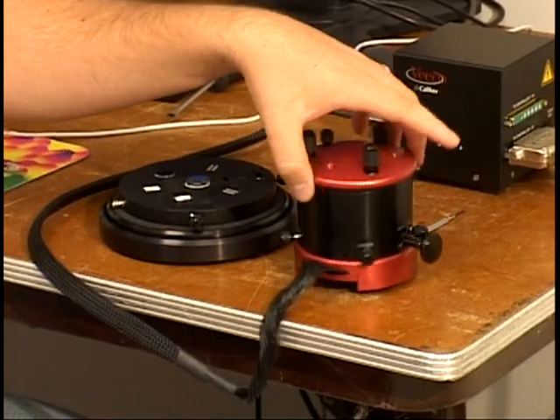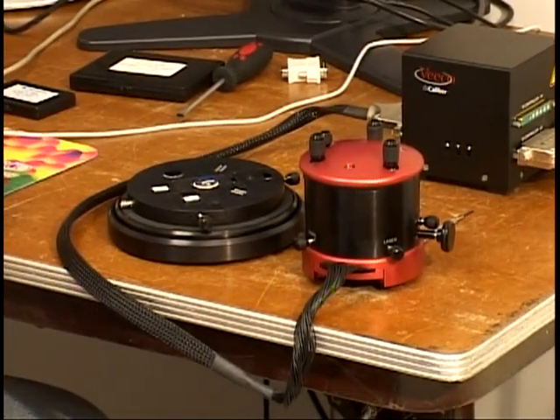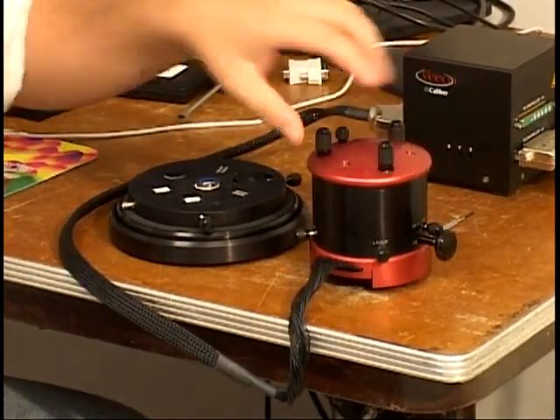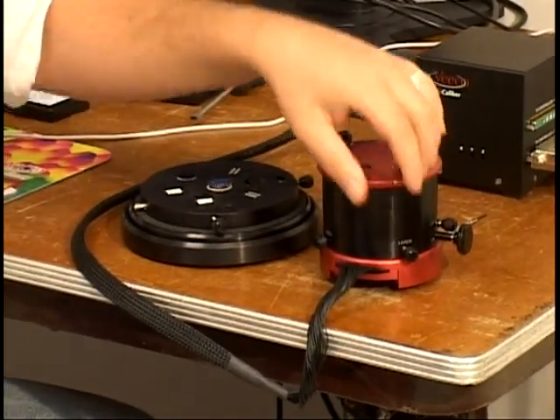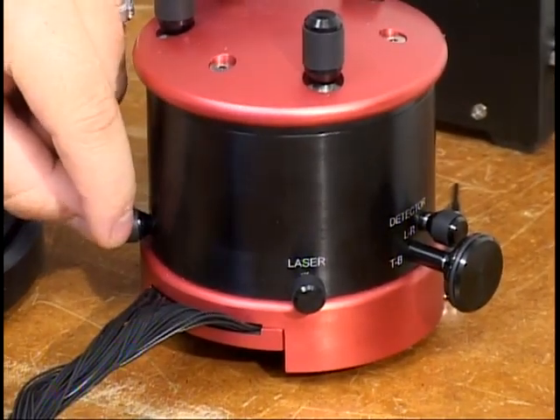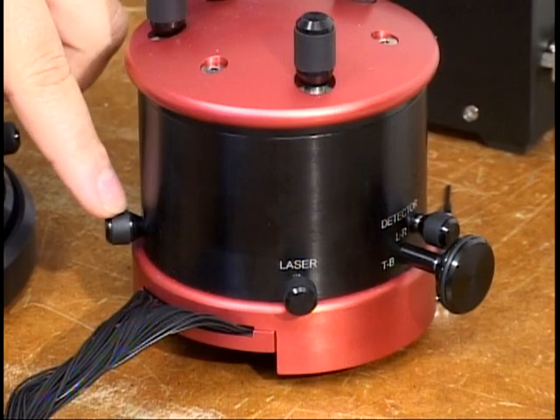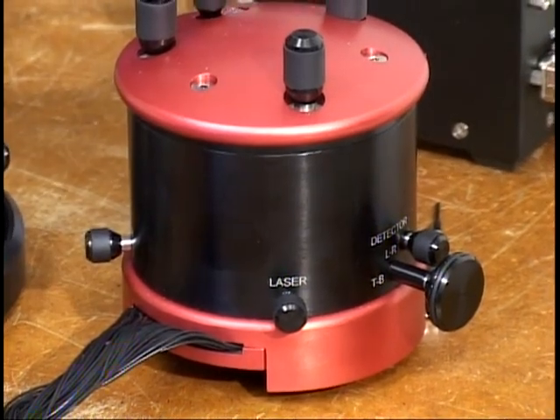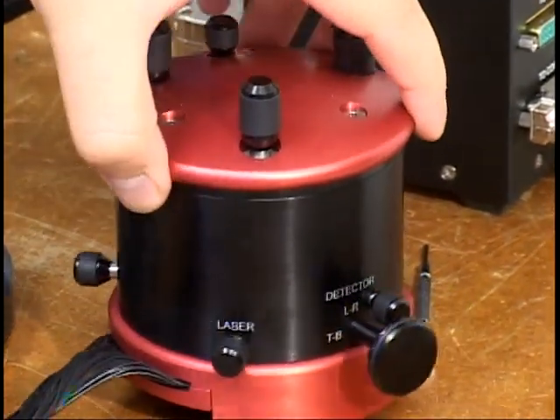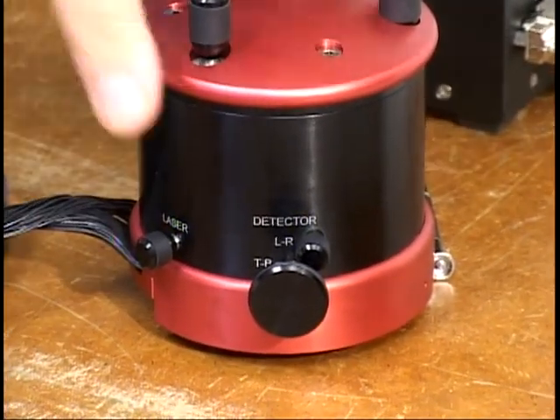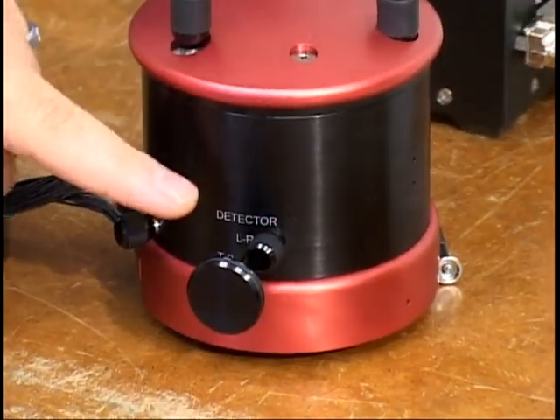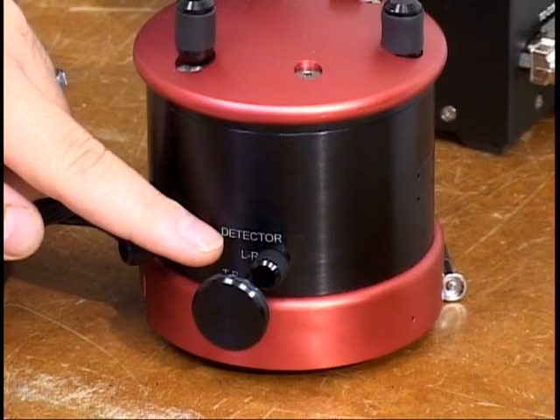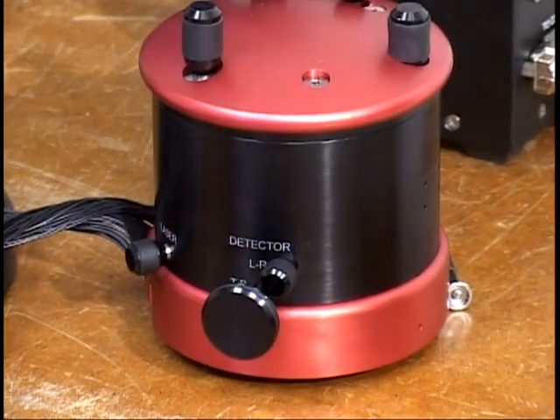Now on this head, we adjust the laser alignment using these two knobs, and we use this to move the laser onto the probe so it can reflect off the probe onto the detector, which we can then use the detector knobs where we can align the laser reflection on the photo detector to get maximum sum.